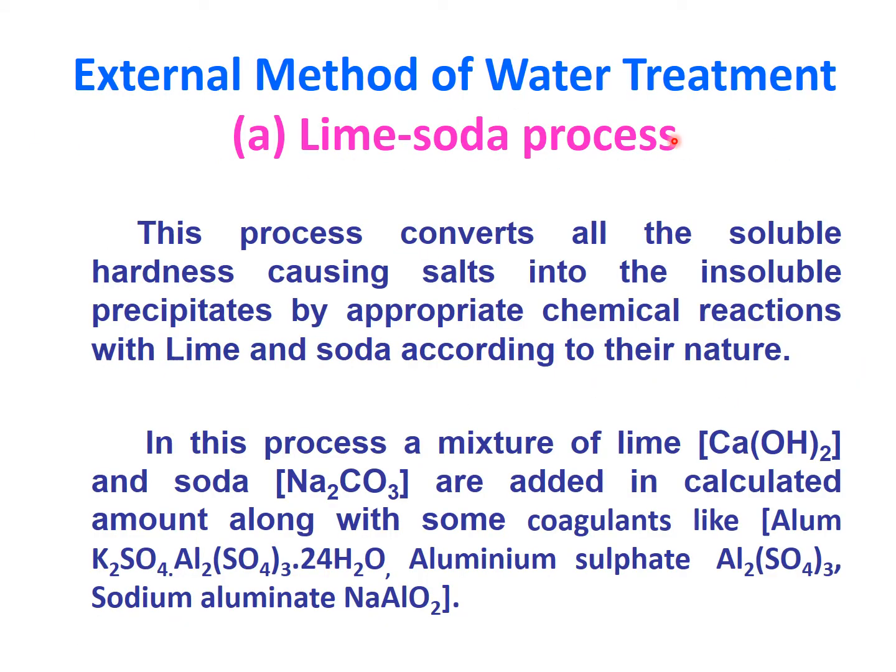As we discussed, in the lime soda process we add a calculated amount of lime and soda according to the hardness present in water. So before starting this process, we have to analyze how much temporary hardness and how much total hardness is in the water, and which salts are responsible for temporary and permanent hardness. According to their amount, we add lime and soda.